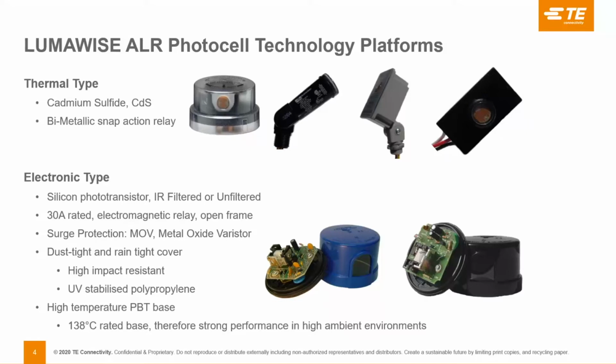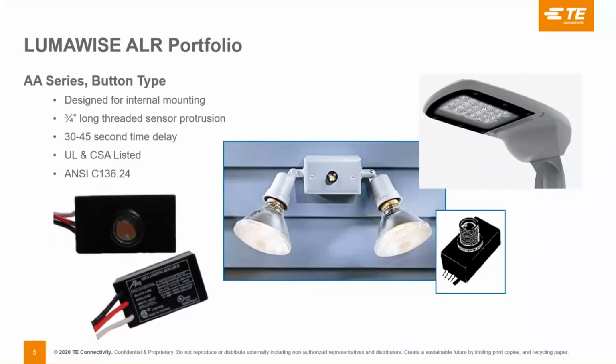In the next few slides, I will discuss TE's preferred product within the LUMAWISE ALR offering. The first preferred product is our AA series button type photocell. It is designed for internal mounting. It has a 3/4 inch long threaded sensor protrusion. It has a 30 to 45 second time delay. It is UL and CSA listed. It also meets the ANSI C136.24 standard.